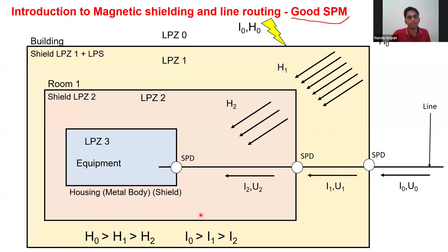Because you have done a very good shielding, this is a good SPM. And since you have put a good SPD and bonded it internally, I0 and U0 will be reduced to I1 and U1, and further reduced to I2 and U2. Here I0 is so much more than I2. So this is a very good surge protective measure done in a building. This is, I would say, a Pakka system.